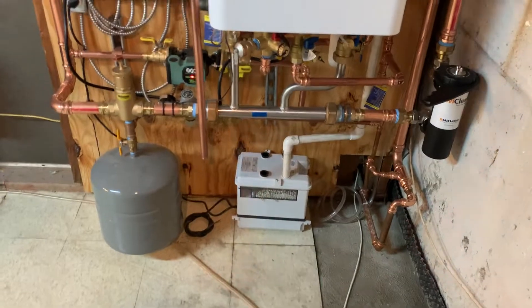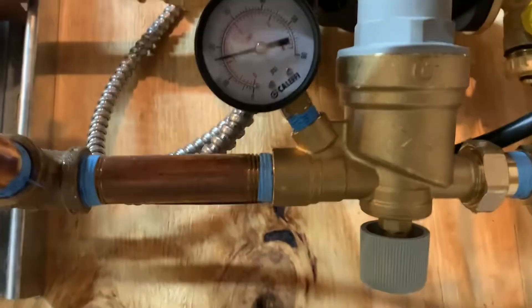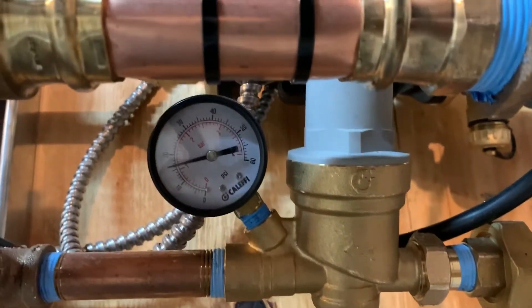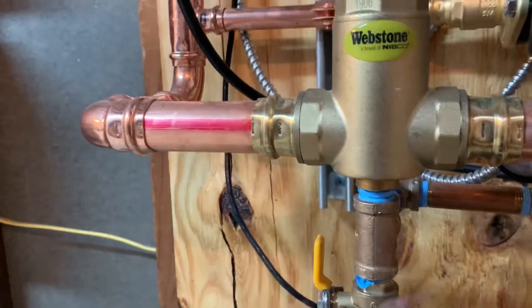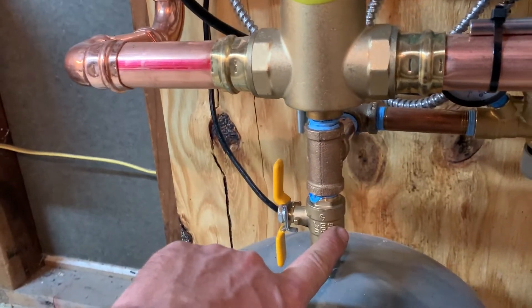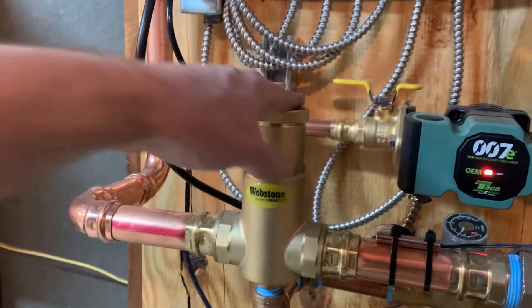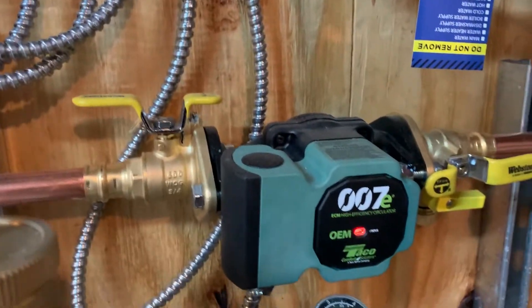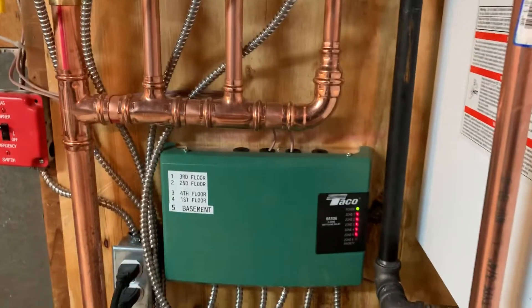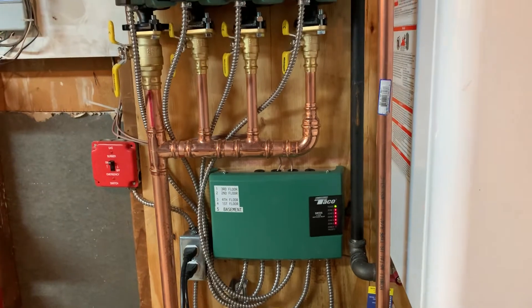We installed the SaniBest condensate pump with built-in neutralizer. We use the Caleffi half-inch pressure-reducing valve with supplemental pressure gauge. We add the Webstone isolation valve for the expansion tank, which makes changing it a breeze when it has to occur. A Webstone inch-and-a-quarter press air separator, and of course our Taco 007e ECM high-efficiency circulators off of the Taco SR506 six-zone switching relay, configured for five zones.